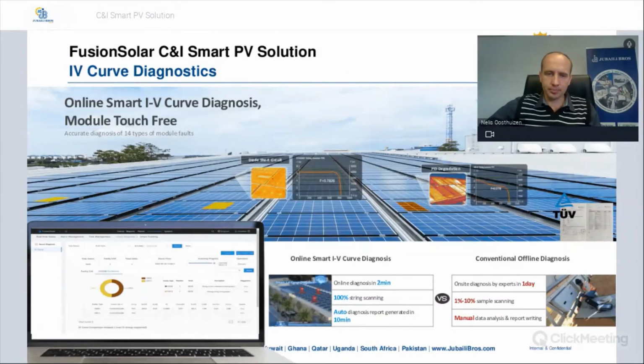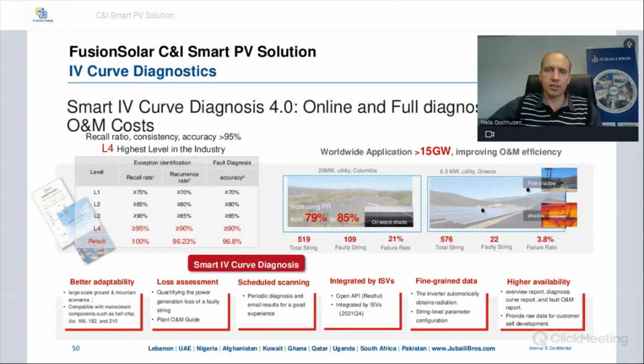It's module touch-free. So if you make use of the online smart I-V Curve diagnosis, the whole system can be diagnosed in 2 minutes, 100% string scanning, and you have an auto-diagnosis report generated in 10 minutes. So if you make use of a conventional testing method, where you have to send the engineer to site to do the testing, it can take you the complete day. Perhaps due to the size of the system, they're only doing certain strings or just sampling. And then also you need manual data analysis and report writing, which can take days or weeks depending on the engineer and availability of personnel.